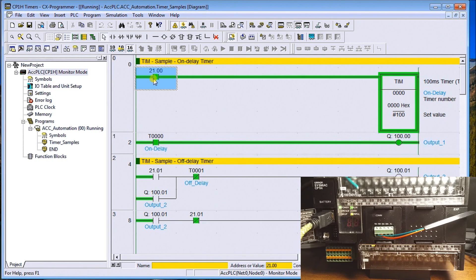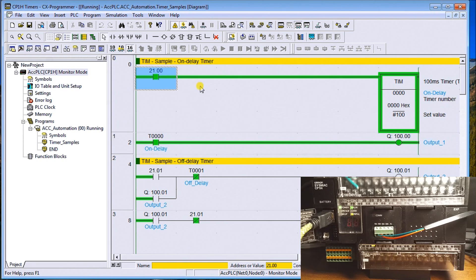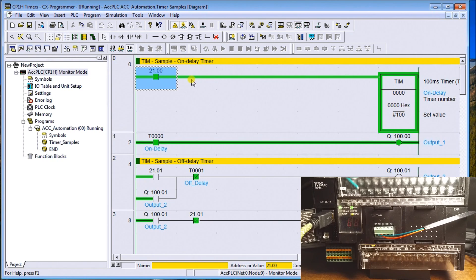That's the on-delay timer. Most timers we deal with are non-memory retentive, meaning that if I lose power to the PLC or go from monitor/run back to program mode, the timer present value is eliminated. The present value is the running countdown of the timer, while the set value is what we want the timer to time to — in this case 100, which represents 10 seconds. In the CP1H we can have up to 4096 timer numbers.